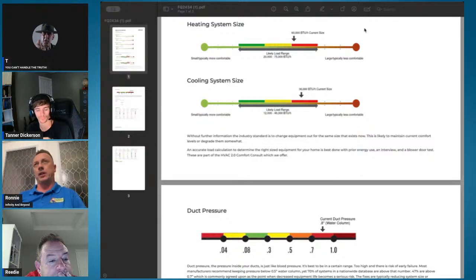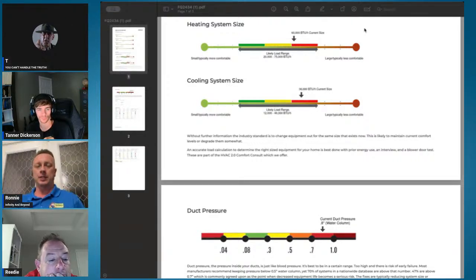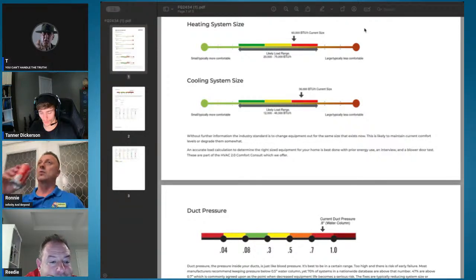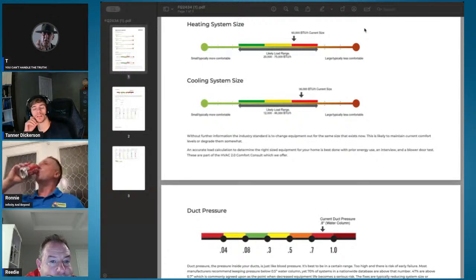It'll run a little. I think it'll probably just run in low for the upstairs most of the time. I could probably even set the control up to where upstairs only calls for single stage cooling, and if the second zone opens, it can stage into the second. That's probably a good idea if he's got it zoned that way.